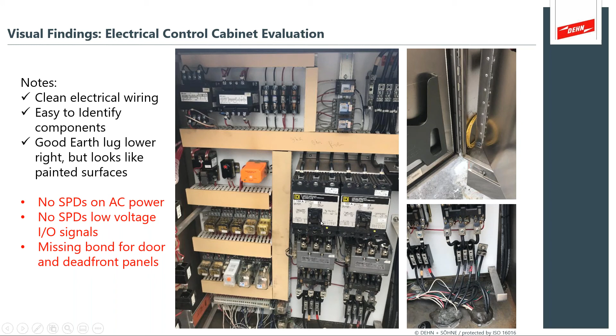We've got some really great illustrations of what to look for. Clean electrical wiring, easy to identify components, good earthing lug right down there in the lower right-hand corner of the panel. But there are some red flags. No SPDs on the AC power. Missing a bond for dead front doors. These are the things that we're looking for. Those are some indications of red flags that the customer will have to come back and offer remediation. So you might be impressed by the cleanliness, it's such a nice layout of the cabinet, but it doesn't have key functions.